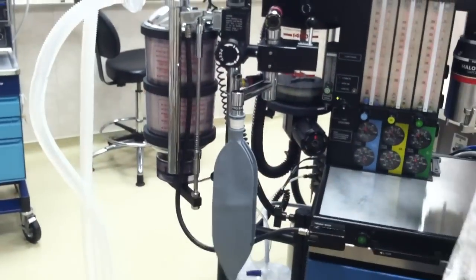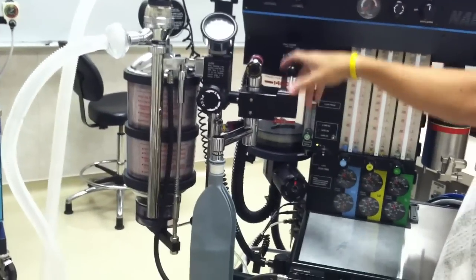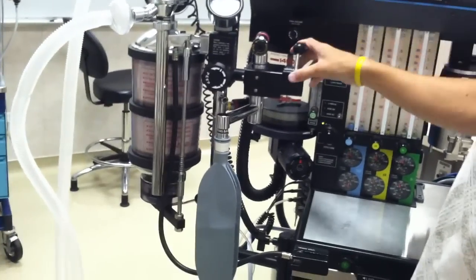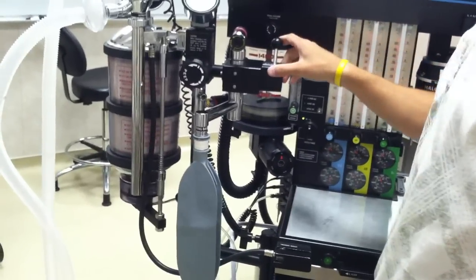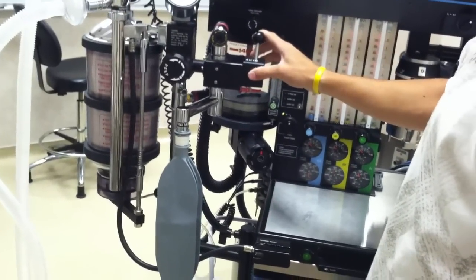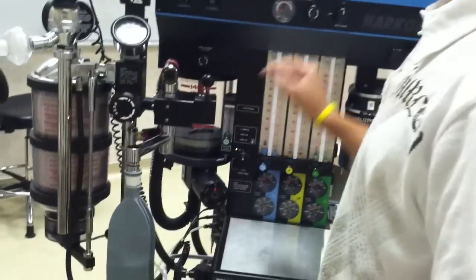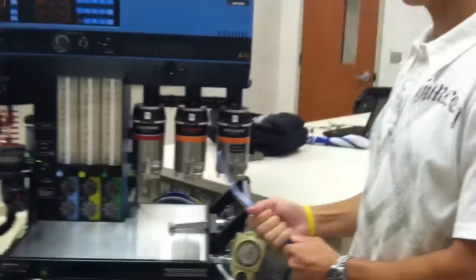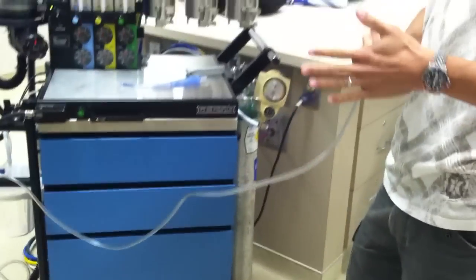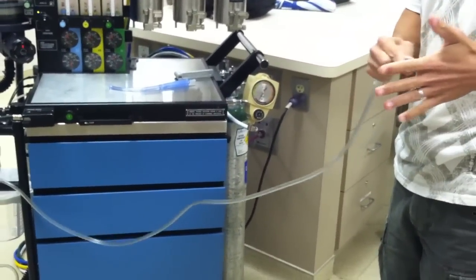So we have two different alarms. That's what we're looking for on this machine. It says apnea pressure and volume. So now that those alarms work, we can go ahead and flip this back over to bag mode and turn off our ventilator. And then we're going to go ahead and check our suction. Turn that to full. Make sure that it can hold suction, which it does.